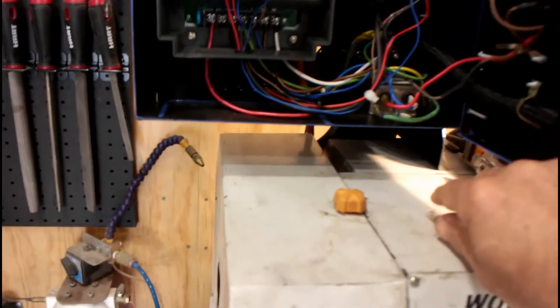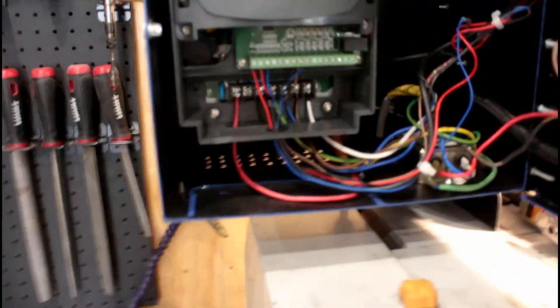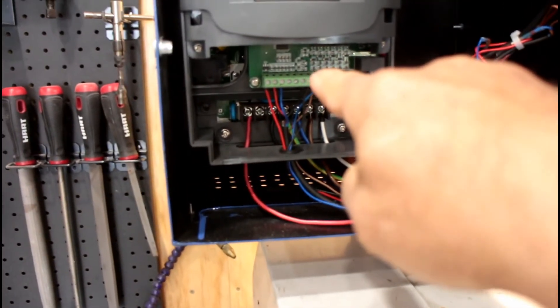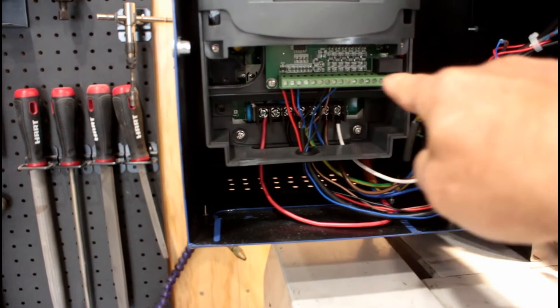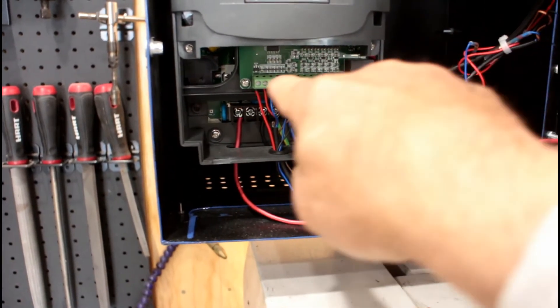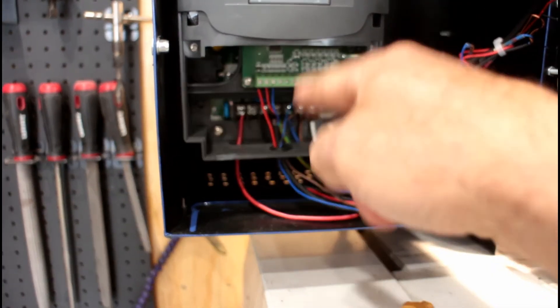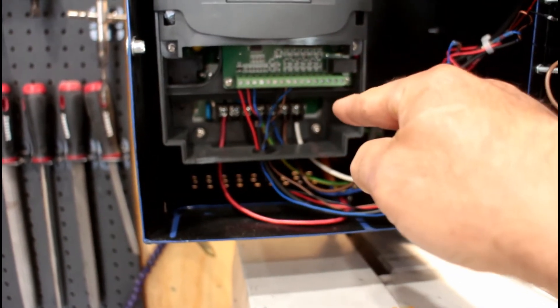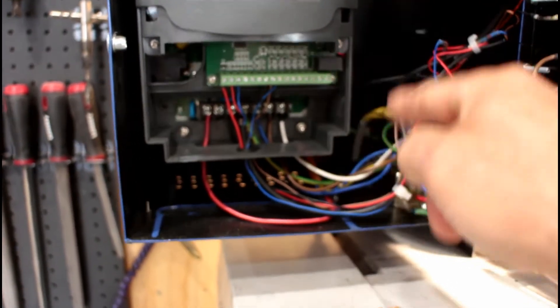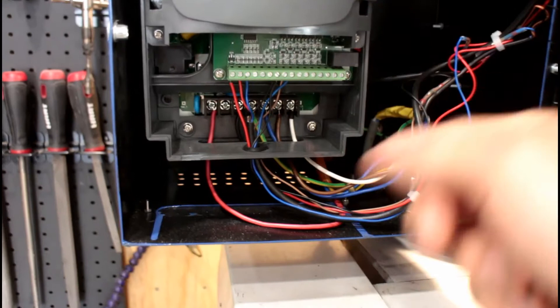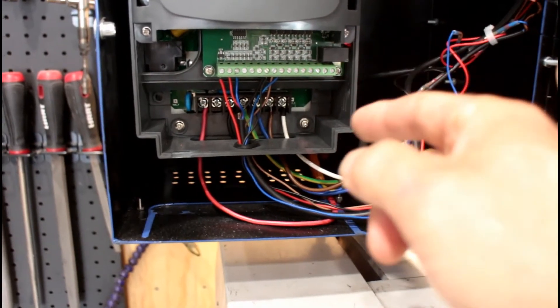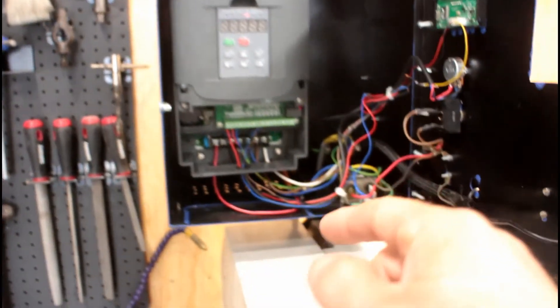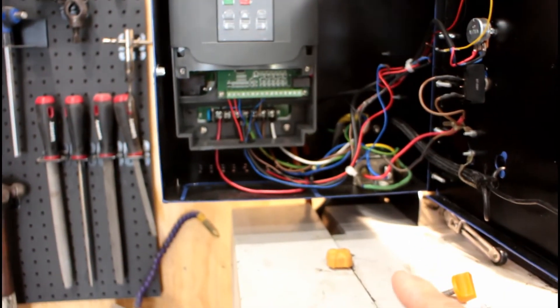I've got the bottom cover taken off just for this filming. A lot of VFDs have two rows of this green connector strip here, which means they have a lot more features. They do have features for switching, adding limit switches, adding interlocks, that sort of thing. This VFD doesn't. It's pretty limited, pretty basic.